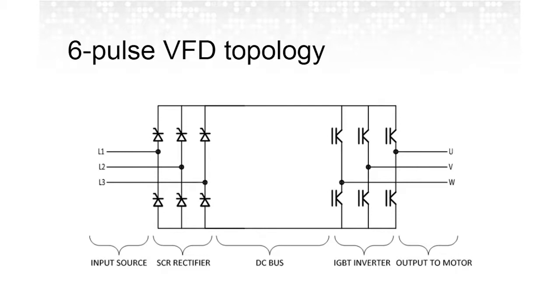Moving on to the most basic type of VFD that the vast majority of applications will see, a 6-pulse VFD. Again, in this diagram, you can see 3 distinct components. You have 3-phase power going into a rectifier section, which again takes that AC power and converts it to DC power on the DC bus. And then from the DC bus, you have another series of switches or IGBTs, which convert it back into that PWM synthesized sine wave. In this simplified diagram, there's a lot of parts that are missing, but it should give you the basic idea of what's going on.